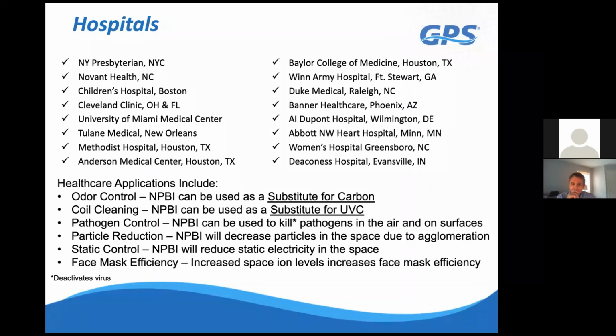And so therefore, if you put these UV lights into your system and you're trying to control COVID-19 in the space, because that's where the actual COVID-19 is, it's going to have no impact whatsoever on the virus in the space. I have found no research anywhere that actually shows that viable virus is actually getting back to the filtration system or UV light systems in these larger HVAC systems.